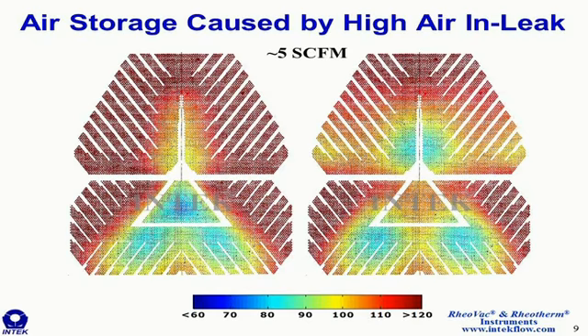This is the performance profile of this condenser with 5 SCFM of air in-leakage. And you can see the color scale at the bottom to let you know what percent of the normalized heat transfer coefficient each region is. So what I want to show you is how this condenser performs, what the performance profile looks like when air in-leakage is increased. So this unit had a ruptured turbine exhaust, a boiler feed pump turbine exhaust flange rupture, and air in-leakage entered through the boiler feed pump turbine exhaust port, which is located on the Bravo side of the shell, roughly where the arrow is shown.